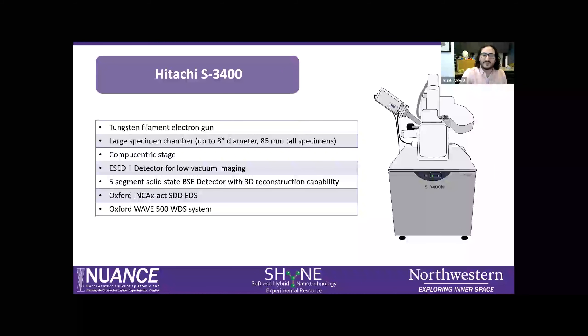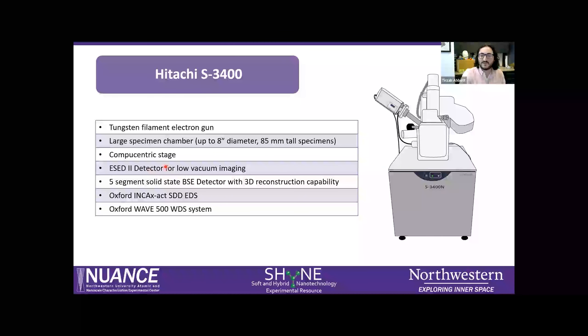The 3400 is also a Hitachi but different from the other two. It's our only tungsten filament SEM, so it's not as powerful as those cold field emission guns. But it has a very large specimen chamber for large samples, a CompuCentric stage, and an ESED (Environmental Secondary Electron Detector) for low vacuum mode to handle charging samples that can't be coated. The 3400 also has a permanently inserted segmented backscattered detector, which is great for 3D reconstructions using different angles. It also has both a solid-state EDS detector and an Oxford Wave 500 WDS system.